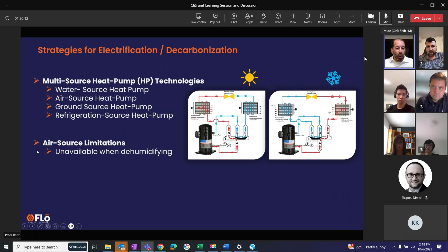One thing to watch out on air source limitations, we're not talking about that for this project. You can't have a water source heat pump or an air source heat pump operating while you're dehumidifying, because you can't run forward and reverse at the same time. So a lot of people along the Gulf Coast, it is actually cold but humid, and they want their heat pump to run, and it just never turns on because they're in dehumidification mode. So that's just something, not that it will affect us.